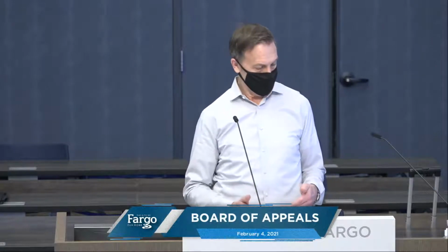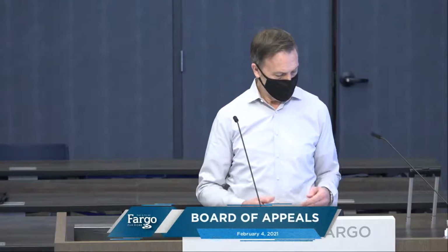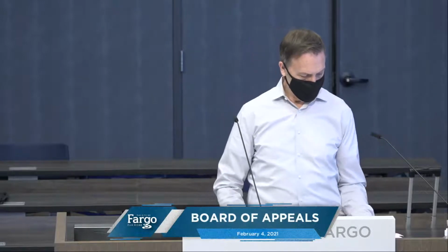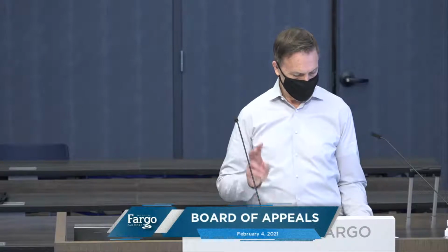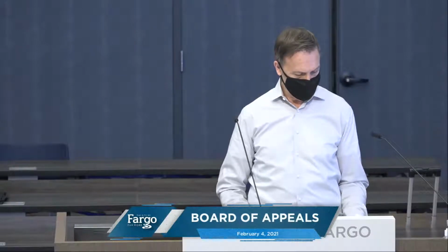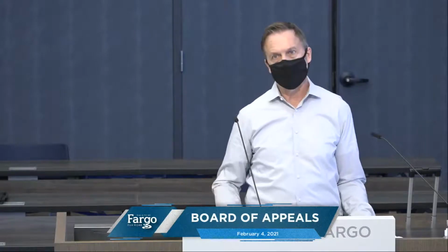Bruce talked about types of vehicles used. There are prohibited uses of open parking garages: vehicle repair, buses, trucks, similar vehicles, partial or complete closing of openings, dispensing of fuel. This section reinforces the concepts and requirements of 406.5.1 and the definition of open parking garages. Any other use or alteration of an open parking garage which is designed to take advantage of increased heights and areas is specifically prohibited.